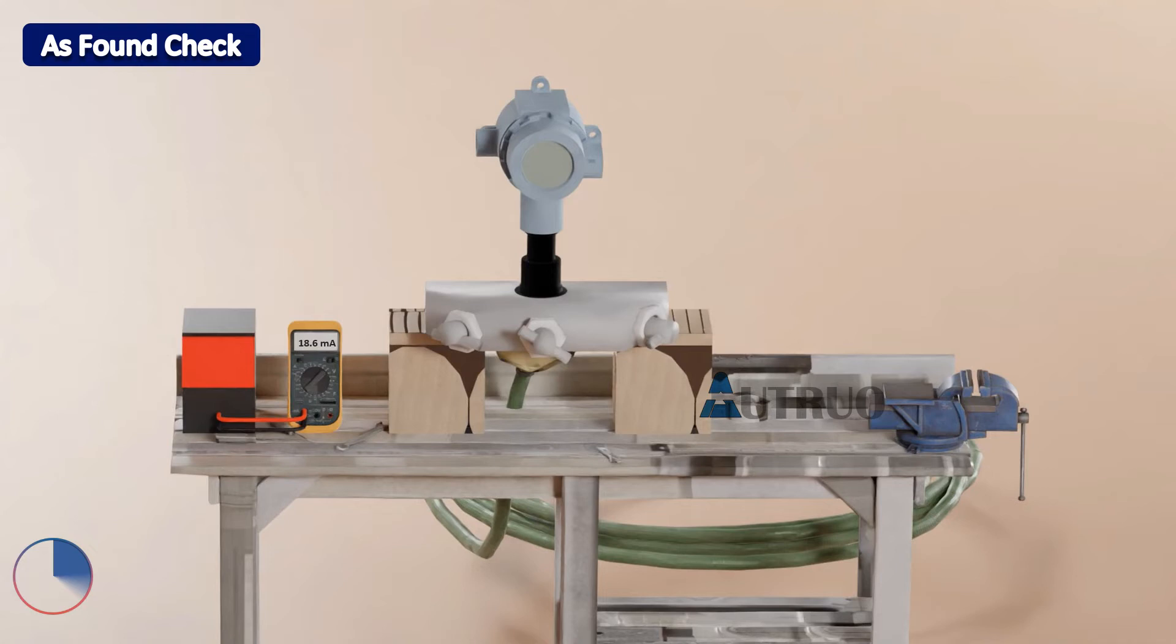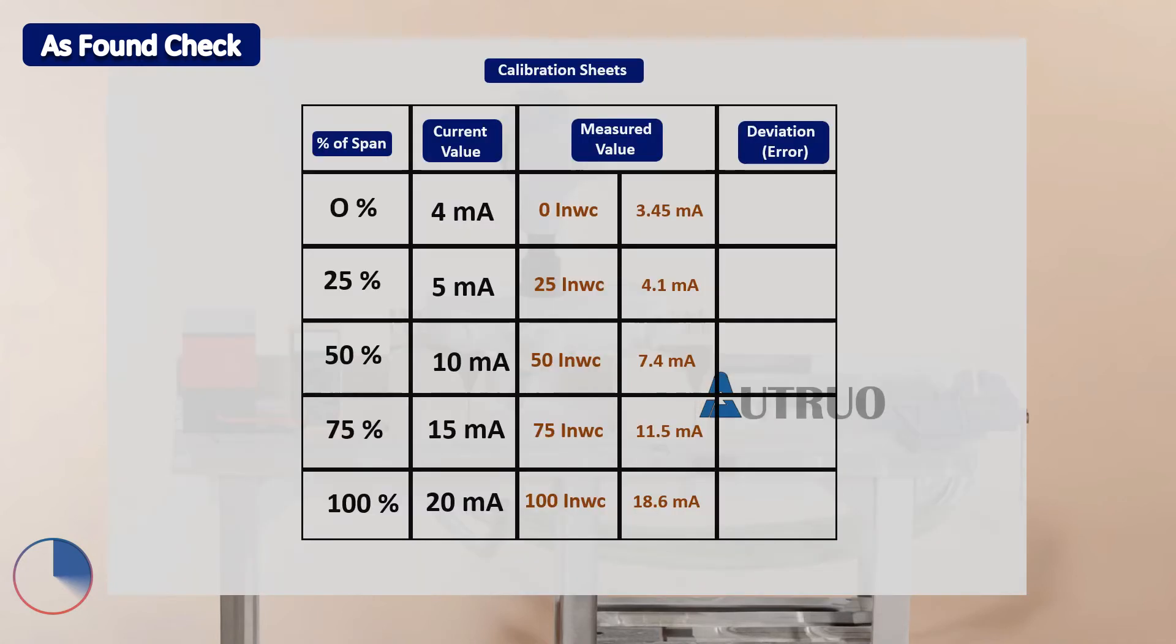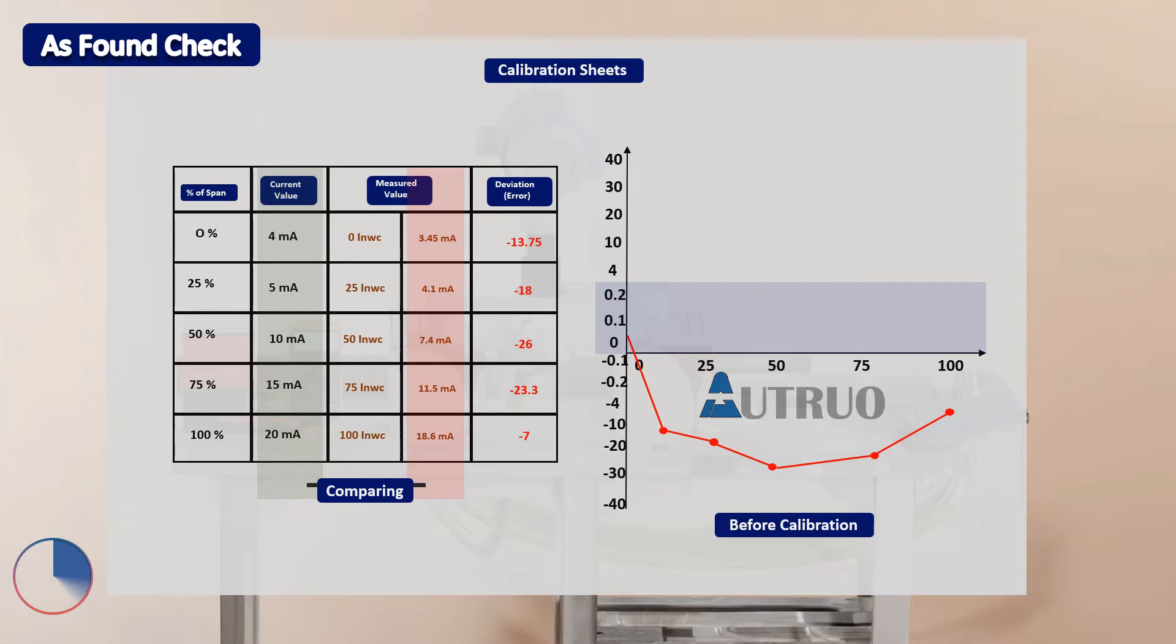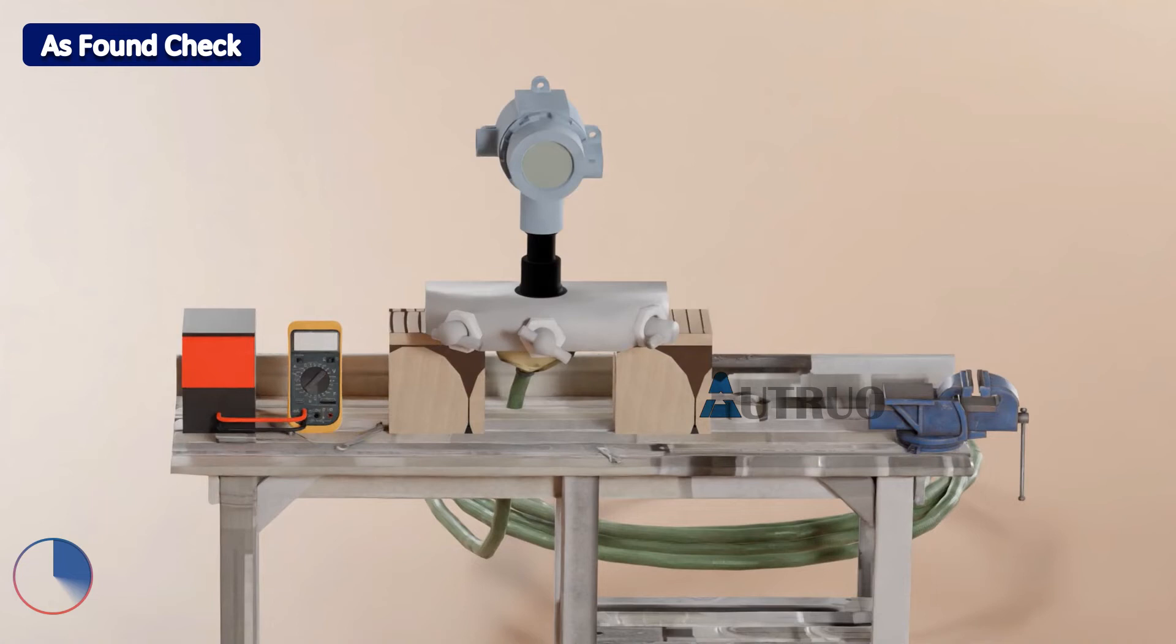Now let's compare all these values with the transmitter documents. As we can see, the current signal is far from what is expected as per manufacturer requirement. Again let's plot all these values on a graph for better understanding. As we can see from the graph, the current state of the transmitter is far from the range that is specified by manufacturer. Hence there is need for recalibrations.